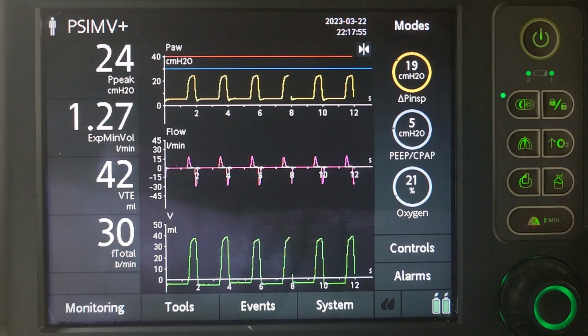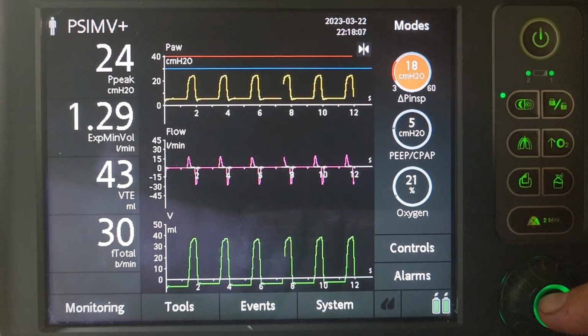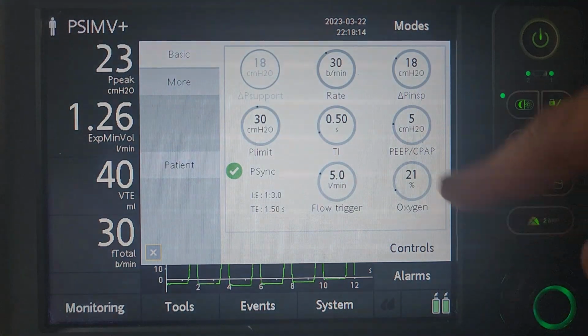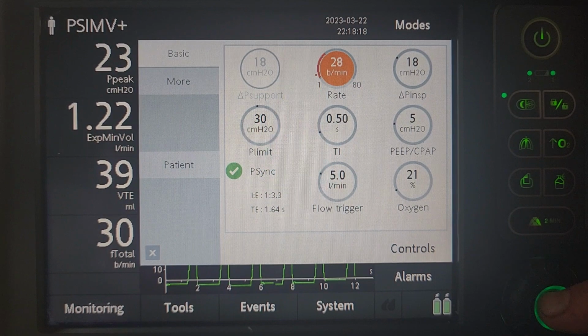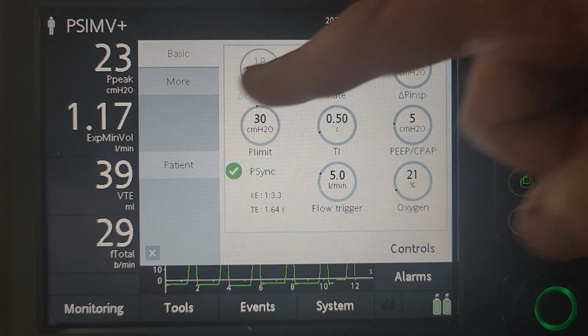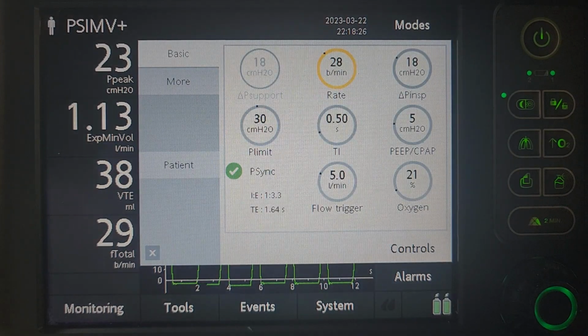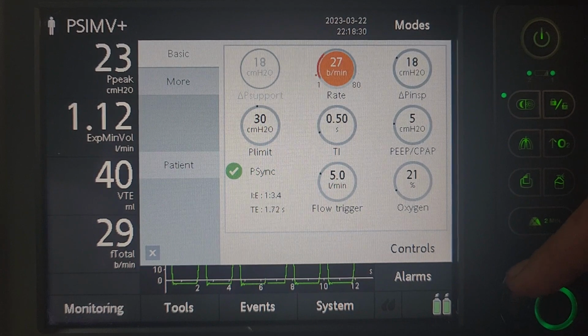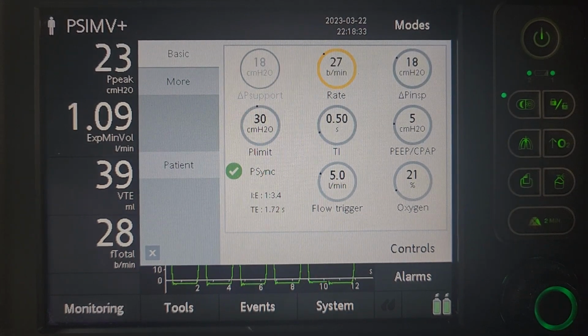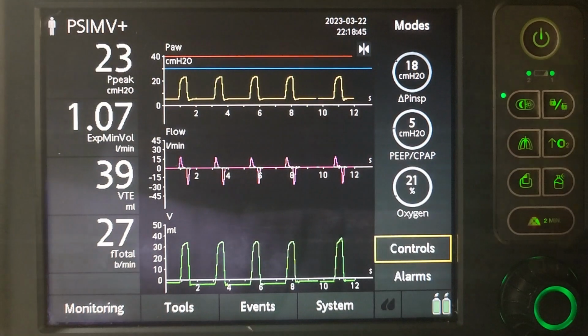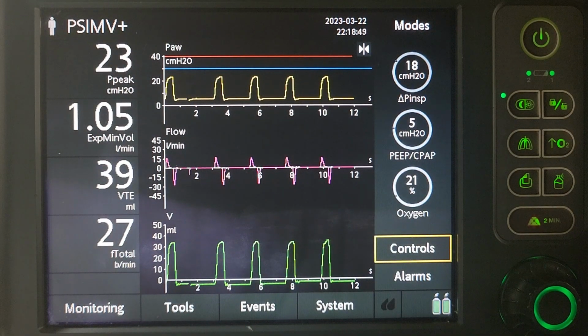Expiratory minute volume is slightly high. If our end tidal CO2 is dropping too far and we're blowing too much CO2 off, we could potentially go down just a little bit with the pressure. Or to decrease our expiratory minute volume here, we can go to our controls and we can decrease our rate just a little bit. And you can leave it right on this screen here and you can watch the changes there. So we're at 28. I want to decrease the expiratory minute volume slightly. And you can see that that's going down. And we're still maintaining around 8 mLs per kilo for our total tidal volume. That's with a standard healthy lung, normal patient.